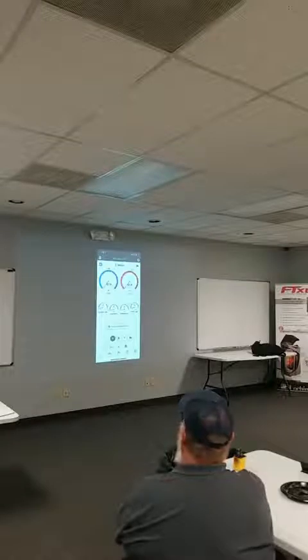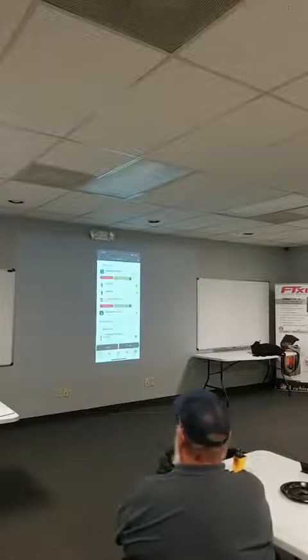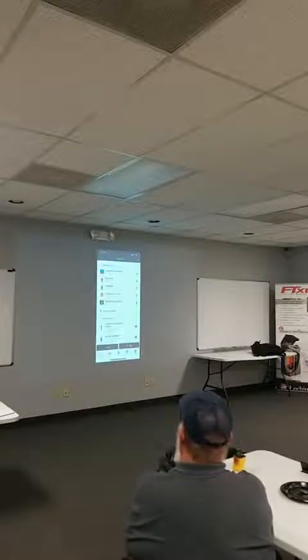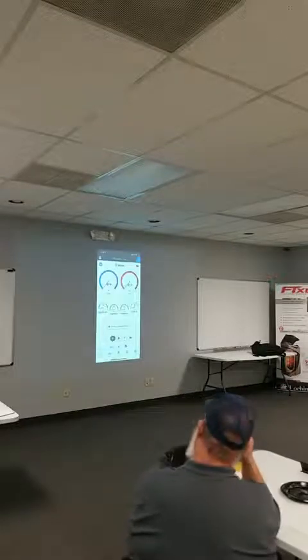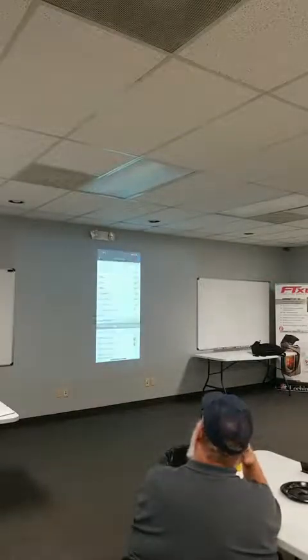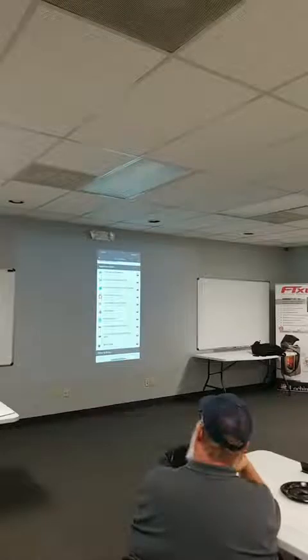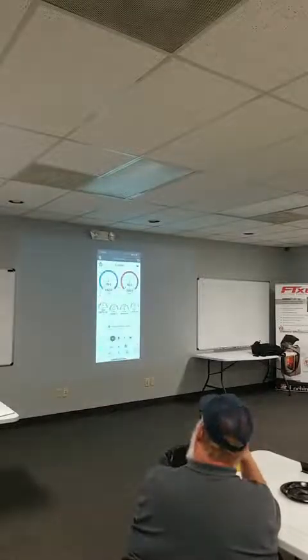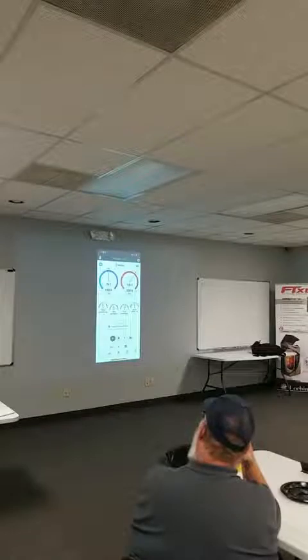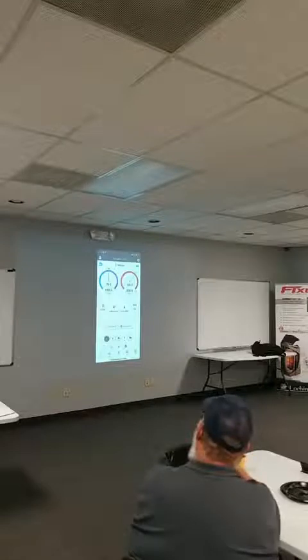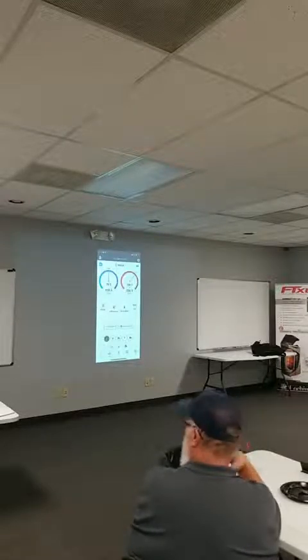I'm gonna deactivate the probes for a minute and throw some demo data in. There's a gear up at the top here. If you tap on that gear and scroll down, you can put in normal operation for a system, and that's gonna throw some targets in there. Now, you'll notice that these targets aren't the same anymore, they're a little bit bigger. And what I did here was set up the airflow on the suction side, because we were having a lot of people who weren't setting the airflow up for a piece of equipment.